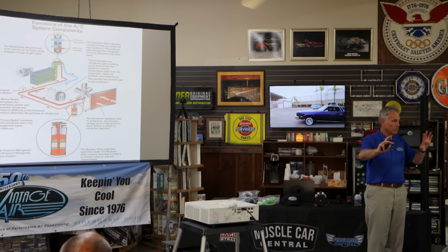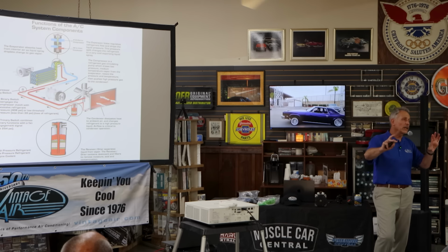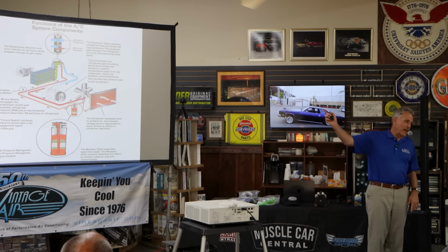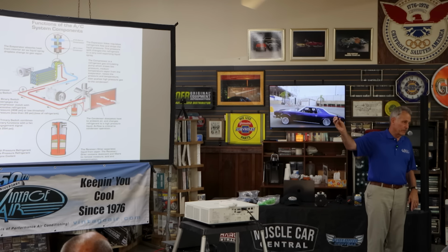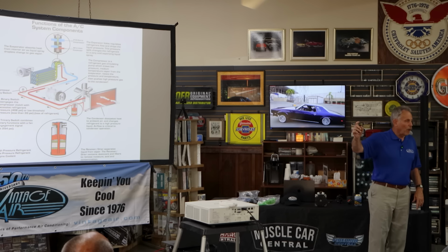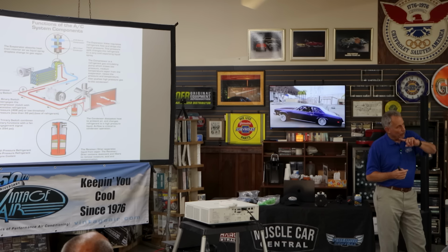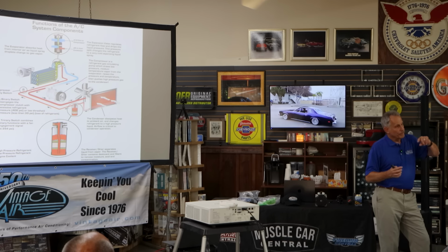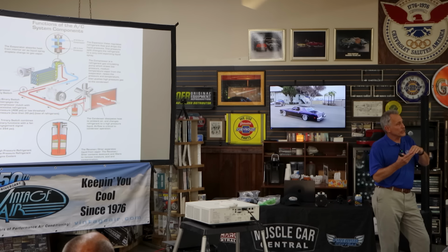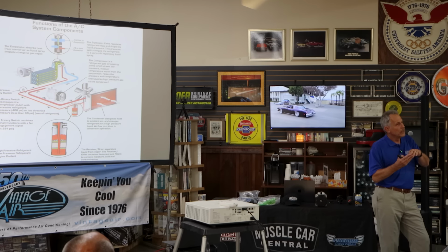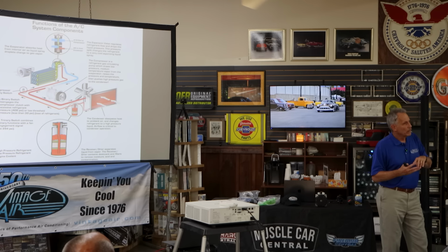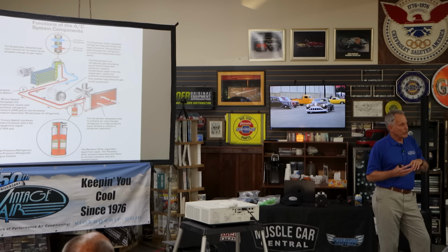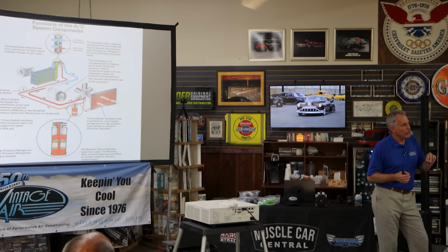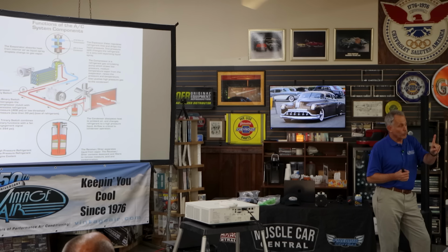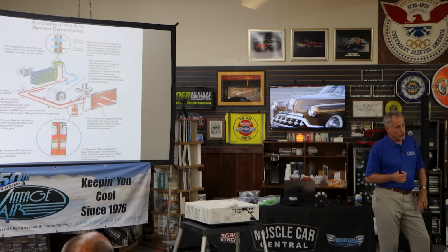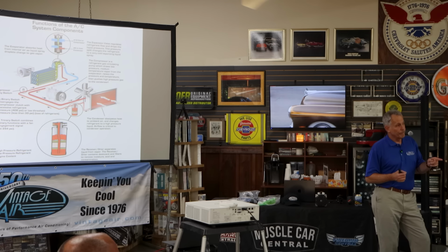So you bypass the relays? No, you still need the relay, because the computer doesn't have the current capacity to handle a fan. All you're doing is joining them on the fan side of the relay. Is it two relays or a single relay? You've got two relays. You're not bypassing those; you're making that one signal run both relays so you're engaging both fans at the same time.